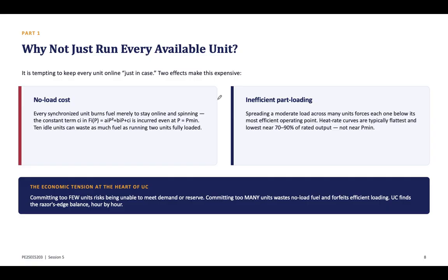So that is the reason it is usually uneconomical. Synchronizing a thermal generator is not a zero cost state. Fuel is required to maintain the steam conditions, auxiliary system operates, rotating equipments remain active, isn't it? And no load components of the production cost is incurred even before the unit contributes substantially useful power. So part loading, we call it as part loading, can also be economically unattractive.